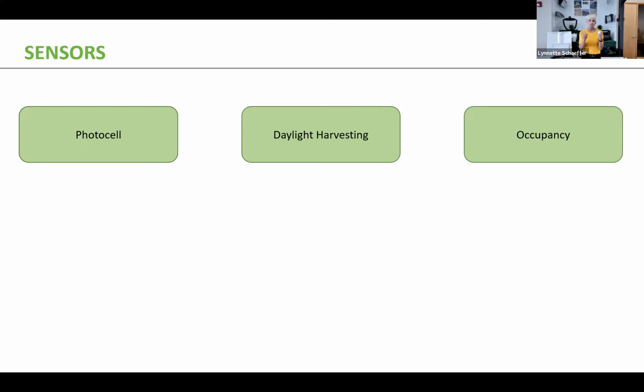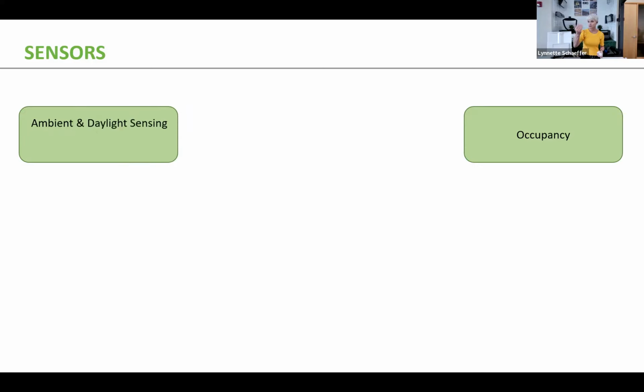That type of technology is actually referred to now as ambient. So if you ever hear the word ambient, think photocell with a few more bells and whistles. For the most part, a photocell back in the day is very similar to an ambient type system. Fast forward to today, you have one sensor that has ambient, and it also includes daylight harvesting, because back in the day you used to have a separate sensor for daylight harvesting and a separate sensor for occupancy sensing. Well, now one sensor actually does it all.